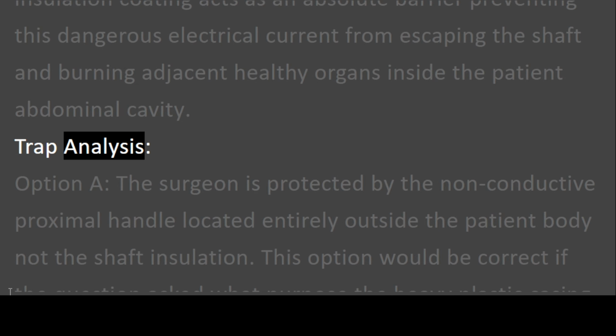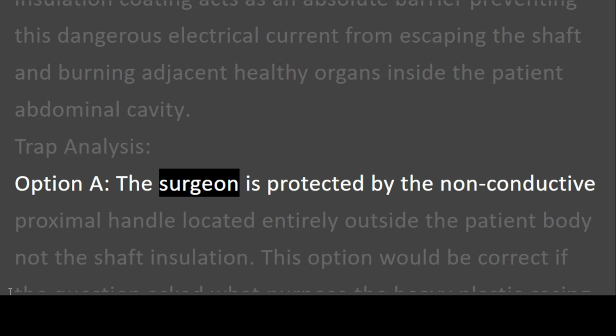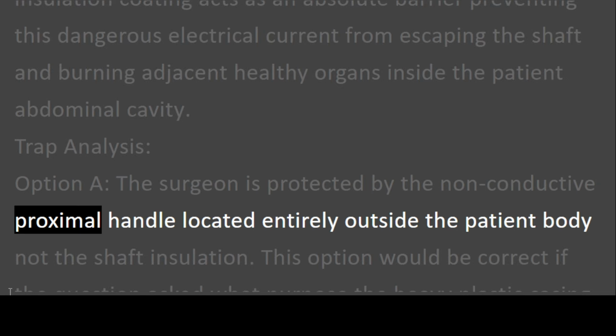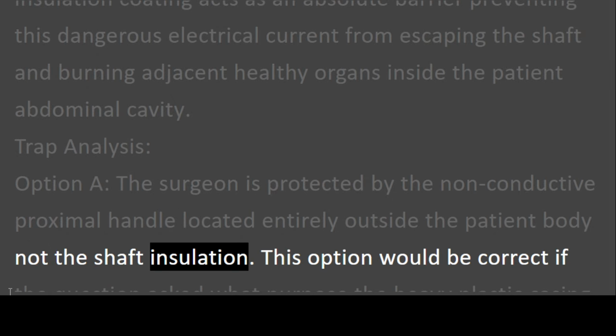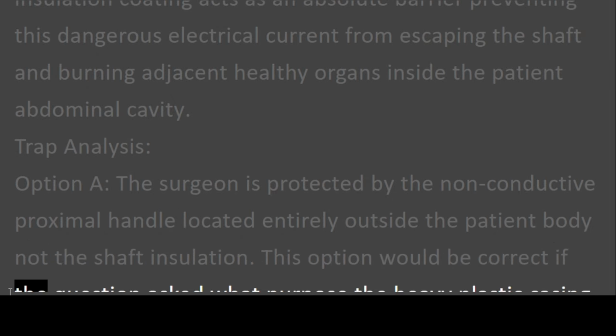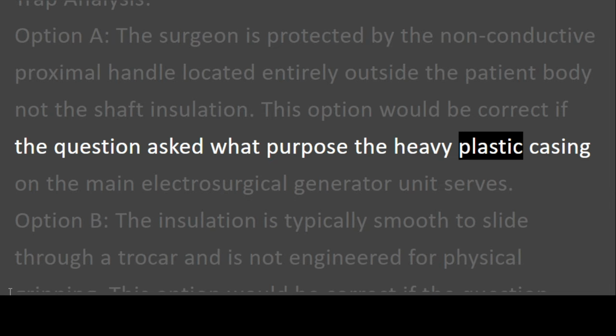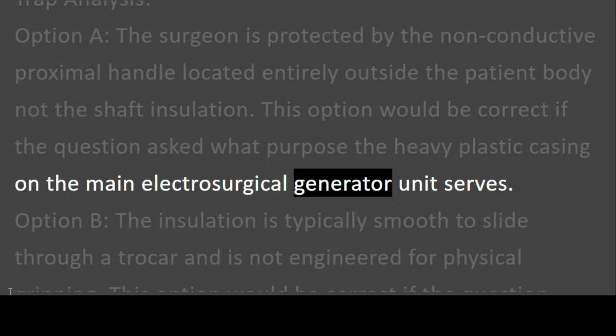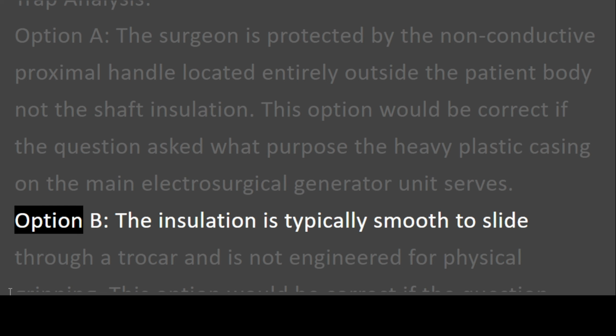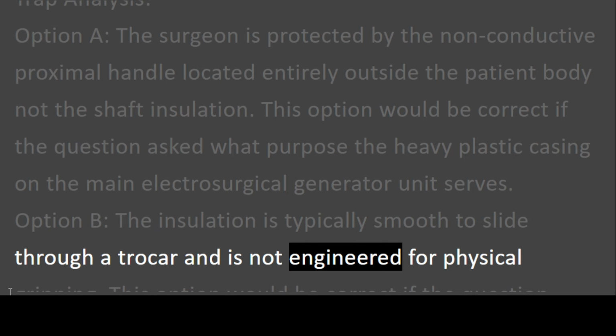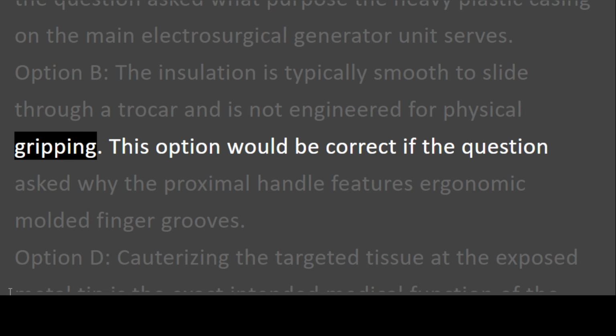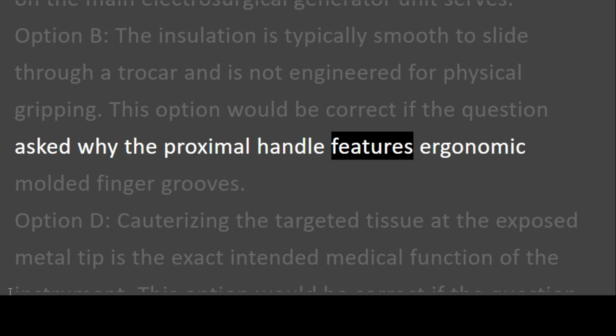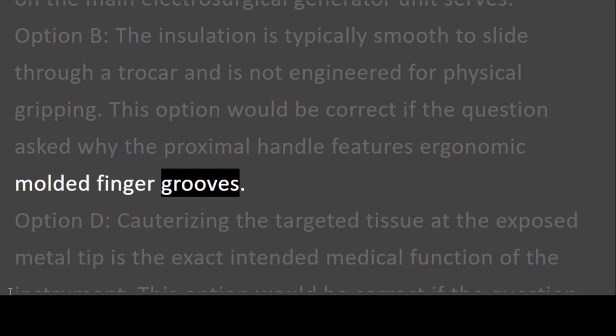Trap analysis. Option A. The surgeon is protected by the non-conductive proximal handle located entirely outside the patient body, not the shaft insulation. This option would be correct if the question asked what purpose the heavy plastic casing on the main electrosurgical generator unit serves. Option B. The insulation is typically smooth to slide through a trocar and is not engineered for physical gripping. This option would be correct if the question asked why the proximal handle features ergonomic molded finger grooves.